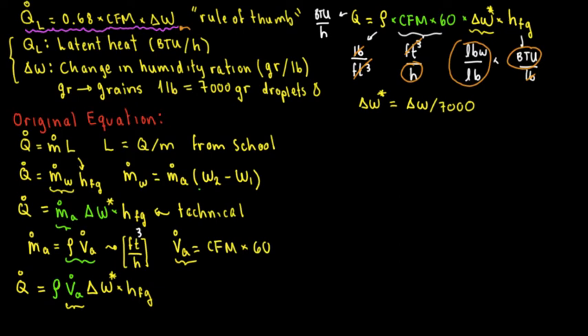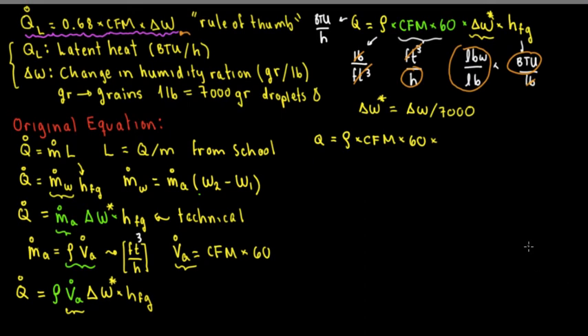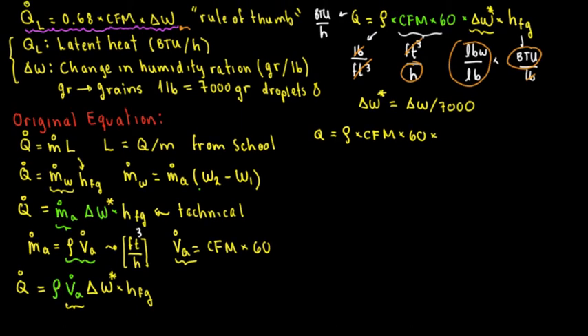So now Q equals density times CFM times 60 times delta W asterisk, but we're plugging in delta W divided by 7,000, times delta h_fg — the specific enthalpy. For air at standard conditions, density equals 0.075 pounds per cubic feet.